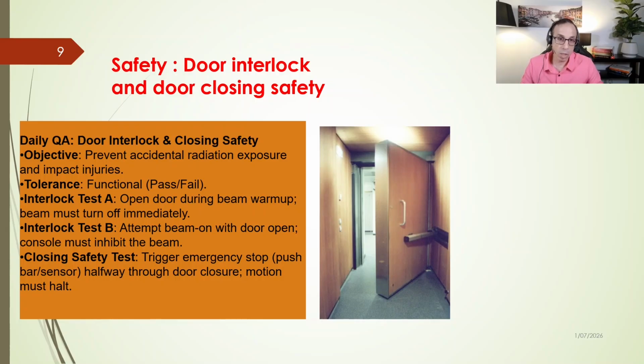To test the interlock system, you will perform two quick steps. First, during your morning beam warm-up, simply crack open the treatment door. The beam must cut off instantly. Second, leave the door wide open and try to turn the beam on from the console. The system must completely block the beam from turning on, and a clear door interlock fault should pop up on your screen. Finally, let's talk about physical safety.